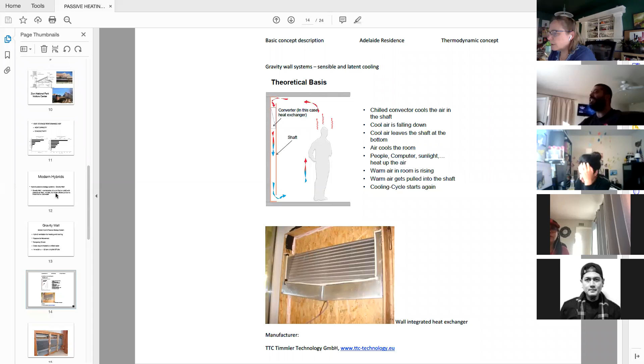So those were generic pictures. This is a picture of the project where I was involved in installing them. This one is a series of three different coils within this wall, which happens to be a half-height wall. In this project, they wanted a more direct feeling in the space sometimes, so they added a fan to help assist the air movement. But we ran a test, and what happens is when you turn the fan on, it makes the air move faster, so it has less time to heat up or cool down. Without the fan, you get more temperature change from top to bottom than you do with the fan, because the air moves more slowly and gradually across the coil, giving it more time for heat exchange.